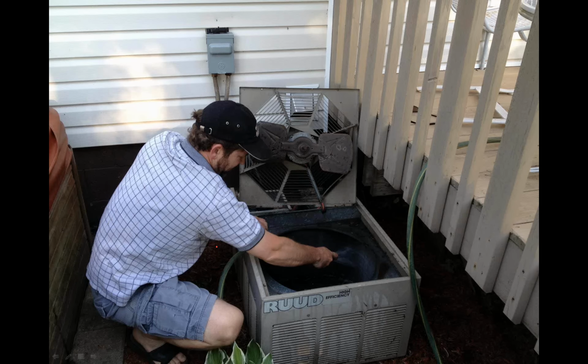and then obviously we also had to go outside and clean the condenser, because his system is an older Rheem system and it's got a fixed orifice in it. With a dirty condenser, you're going to drive up the head pressure. When we drive up the head pressure, we're going to force more refrigerant into the evaporator coil.